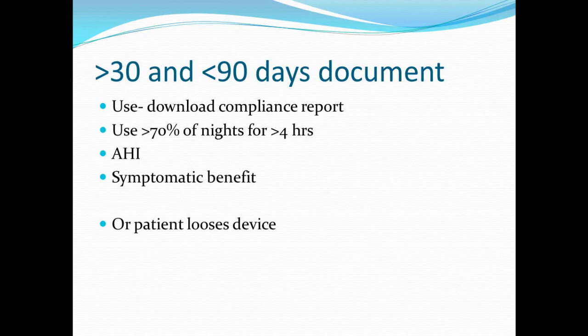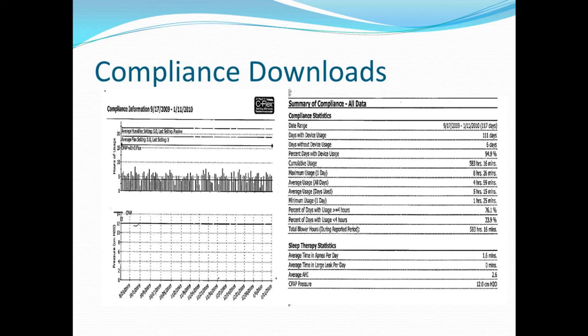Well, how do you tell that? Well, you can ask the patient, but often they won't be straightforward with you because they want to keep the machine. So you get a compliance download. There's a chip in the back of the machine. They can download this, and the DME company can fax you this. This shows the nights, and this is whether they wore CPAP and for how many hours. This is hours here. And then they'll give you days with usage, and they'll give you the percentage of days with usage greater than 4 hours, 76%. And it'll give you the pressure and the apnea-hypopnea index on the CPAP. And this can be very helpful for troubleshooting, too. It often will show you whether there's a big leak.